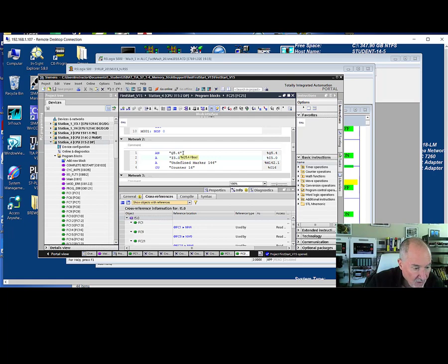So we don't have names for these, but let's say I trace I5.0, and indeed that is a bad sensor or something like that that was not allowing my counter to count. So you'll trace it back until whatever you're looking for kind of appears here. So this can take a little bit of time.